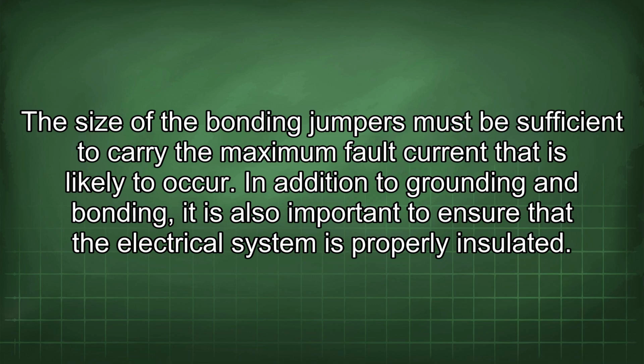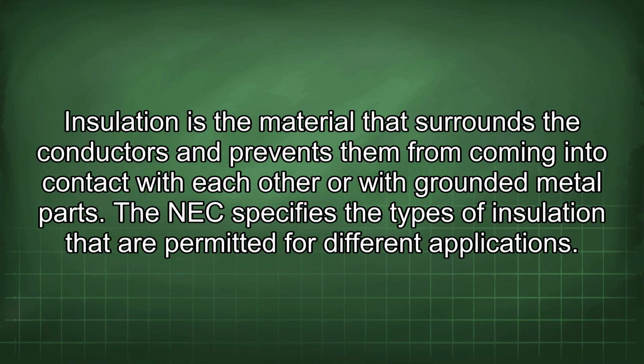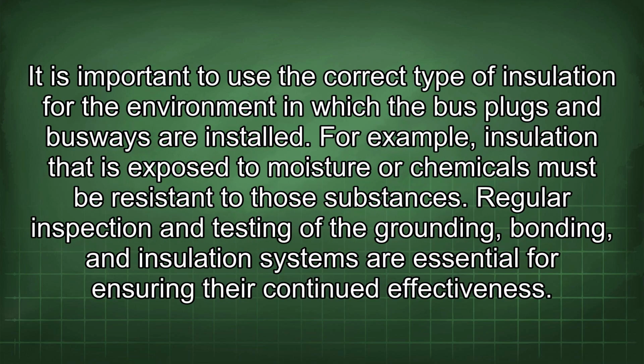In addition to grounding and bonding, it is also important to ensure that the electrical system is properly insulated. Insulation is the material that surrounds the conductors and prevents them from coming into contact with each other or with grounded metal parts. The NEC specifies the types of insulation that are permitted for different applications. It is important to use the correct type of insulation for the environment in which the bus plugs and busways are installed. For example, insulation that is exposed to moisture or chemicals must be resistant to those substances.